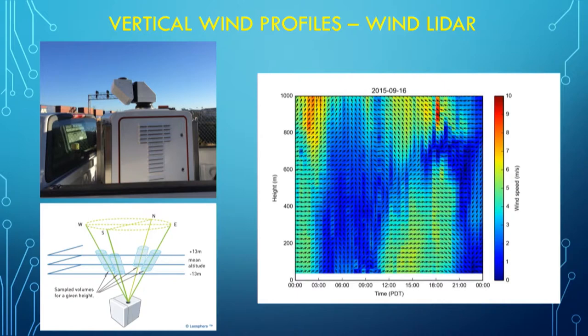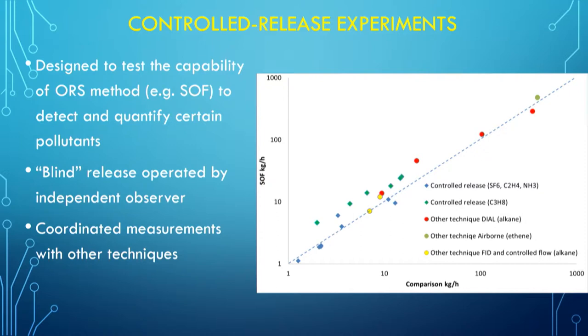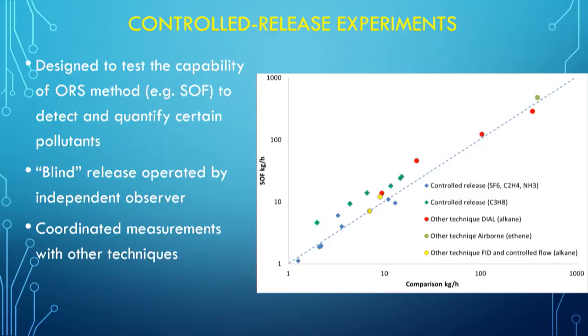To elaborate on the accuracy and precision of the method, the way to validate and verify the approach is to use a controlled release experiment. Over the last 10 to 15 years, many optical remote sensing contractors have been conducting these experiments — you release a known quantity of your target compound, usually in a blind test to quantify what your emission rate is, and then compare it with the true emission rate. Here is an example of a variety of controlled release experiments done by FluxSense with different gases, also compared with other techniques.